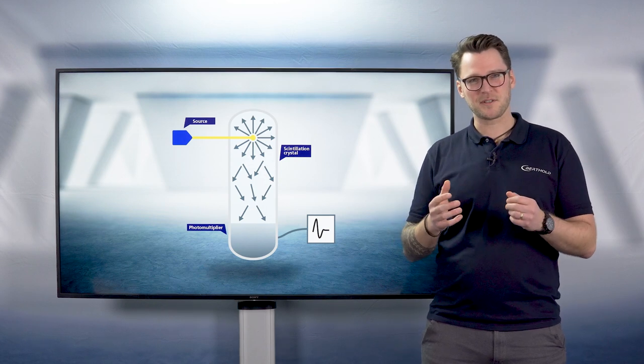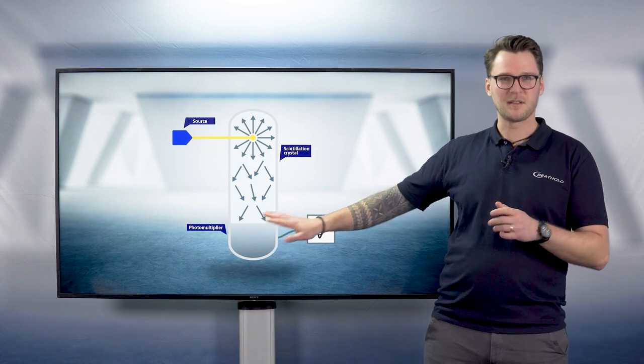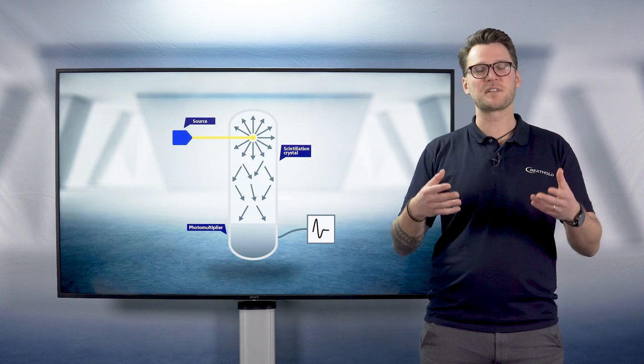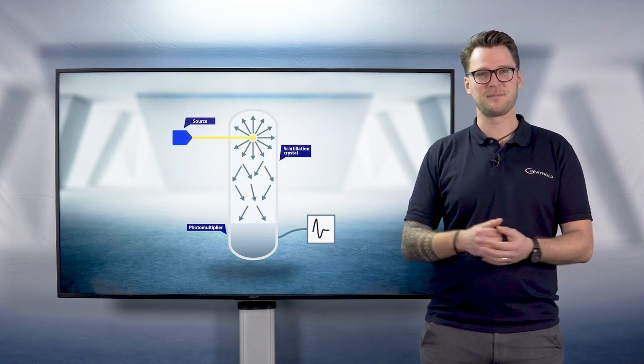Those light flashes knock out electrons at a photocathode at the top of the photomultiplier. Those electrons now get multiplied and converted into a measurable current. This electric current is dependent on the amount of incident radiation hitting the detector.